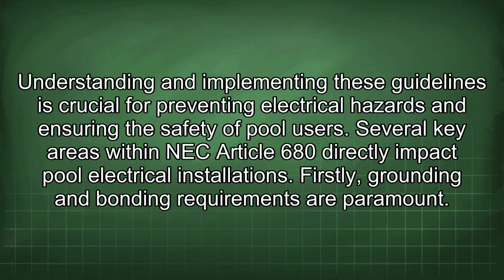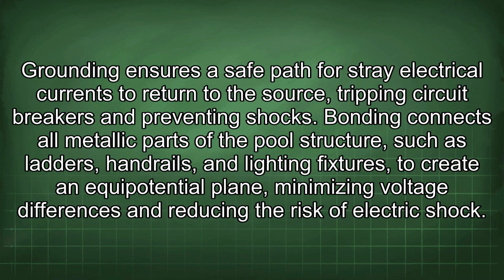Firstly, grounding and bonding requirements are paramount. Grounding ensures a safe path for stray electrical currents to return to the source, tripping circuit breakers and preventing shocks. Bonding connects all metallic parts of the pool structure, such as ladders, handrails, and lighting fixtures, to create an equipotential plane, minimizing voltage differences and reducing the risk of electric shock.